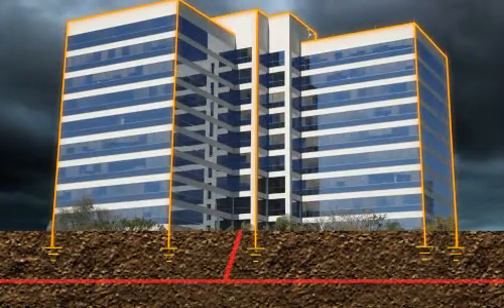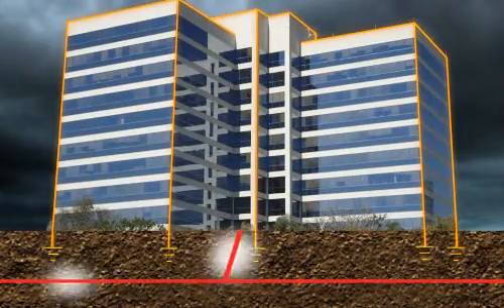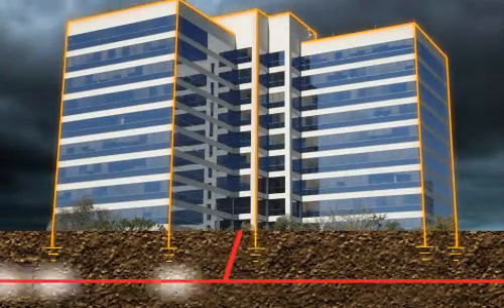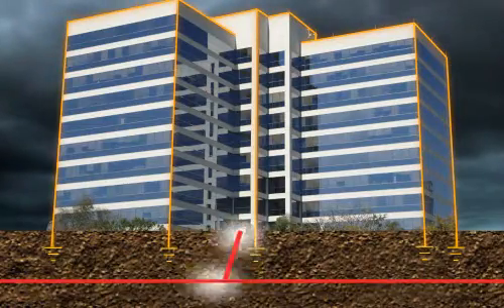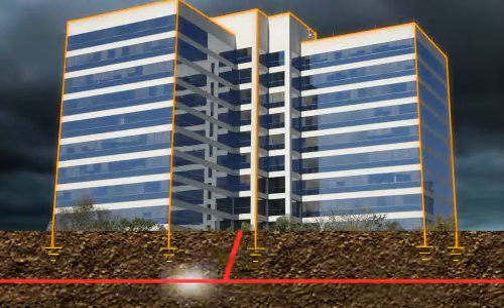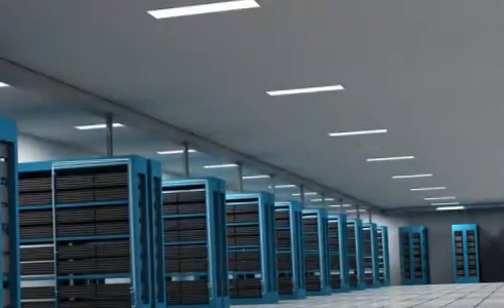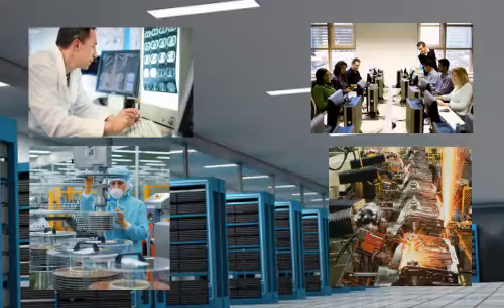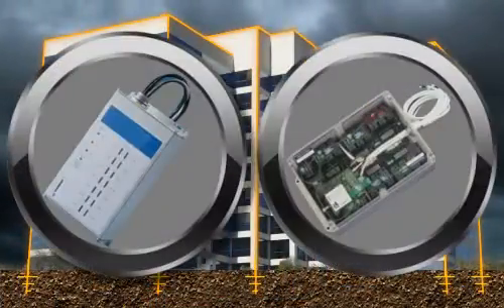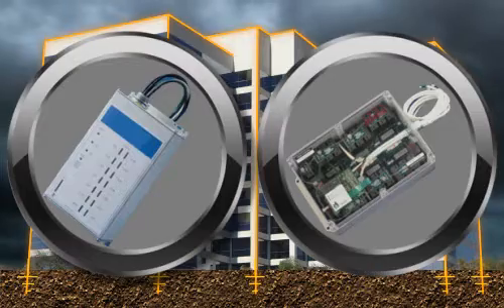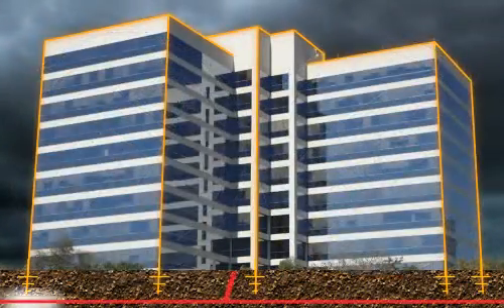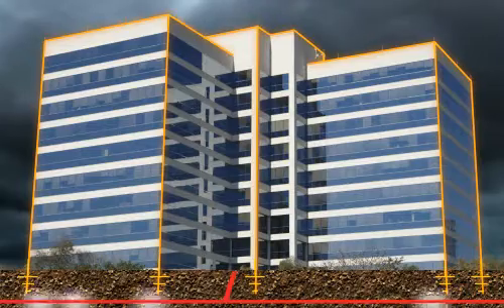Direct strikes are not the only dangerous threat created by lightning. Surges created by distant lightning strikes destroy sensitive electronics and appliances. In order to protect equipment such as networking equipment, servers, computers, telephones, and other media, surge protection devices or SPDs must be installed at the main electrical panel, telephone, and other service entrances.